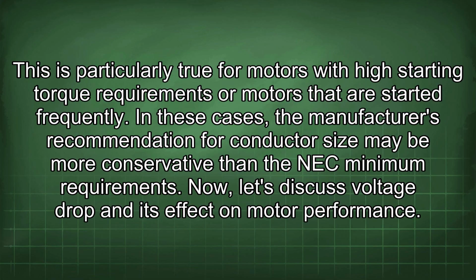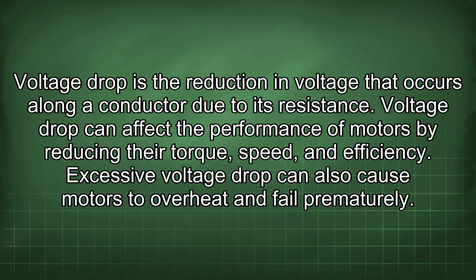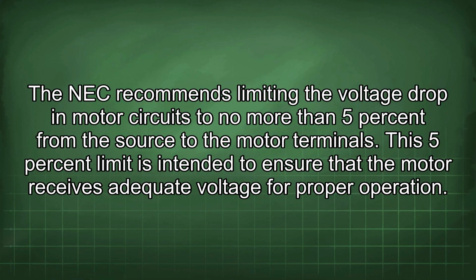Now let's discuss voltage drop and its effect on motor performance. Voltage drop is the reduction in voltage that occurs along a conductor due to its resistance. Voltage drop can affect the performance of motors by reducing their torque, speed, and efficiency. Excessive voltage drop can also cause motors to overheat and fail prematurely. The NEC recommends limiting the voltage drop in motor circuits to no more than 5% from the source to the motor terminals. This 5% limit is intended to ensure that the motor receives adequate voltage for proper operation.